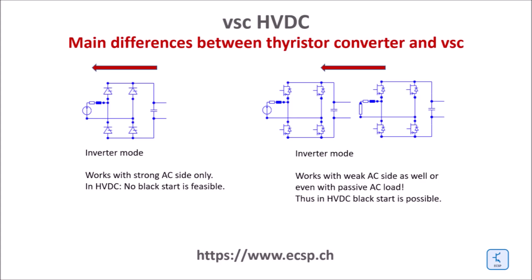First, a thyristor inverter can work with a strong AC side only; otherwise the commutation between one leg of the bridge and the other leg does not work. The commutation is needed because one leg is fired whilst the other leg is still conducting. Thyristors interrupt current only when it passes zero, thus an AC source is needed for commutation.